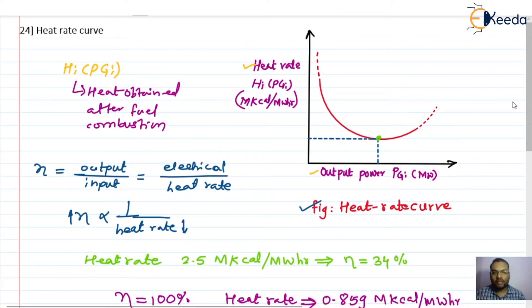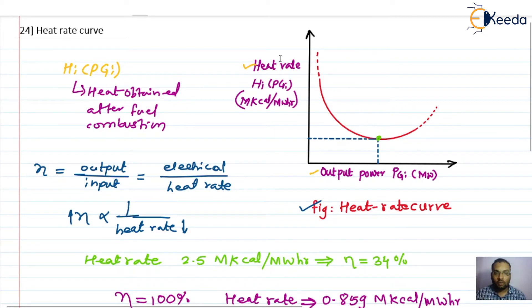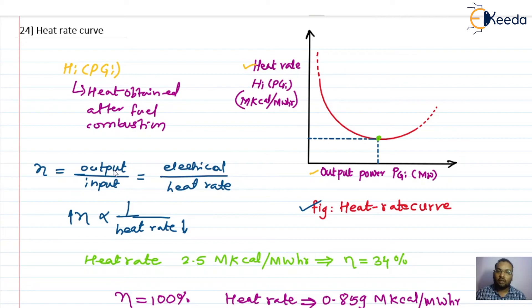Now, why is this heat rate curve useful? We study it to decide the operating point of the generator, because we always want the generator to operate at the highest possible efficiency — that is, minimum input for maximum output. With the help of this heat rate curve, we can find the coordinate where the efficiency of the alternator or generator will be maximum.